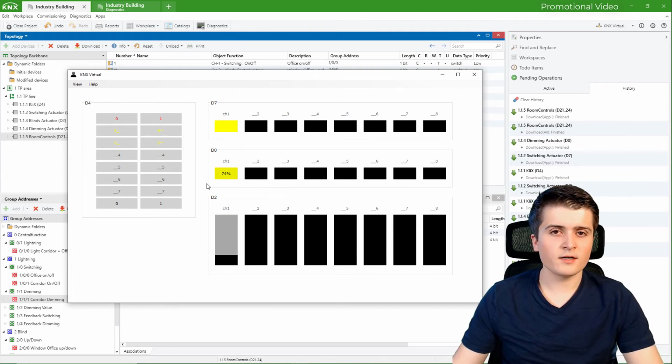And now the second device might not be a push button sensor, but for example, a visualization panel or a presence detector or motion detector that you just hook up to the corresponding group address, and then the only thing that you have to parameterize is the new device itself and no other existing device.